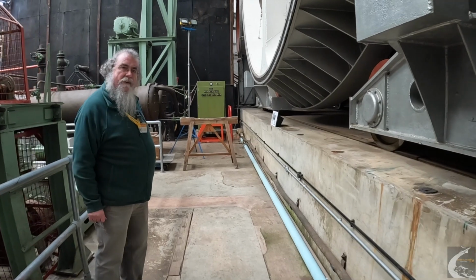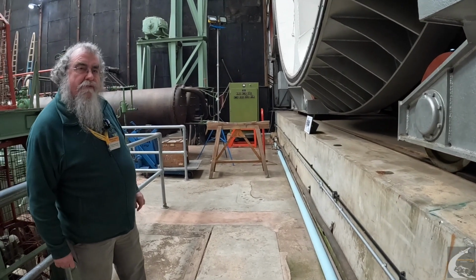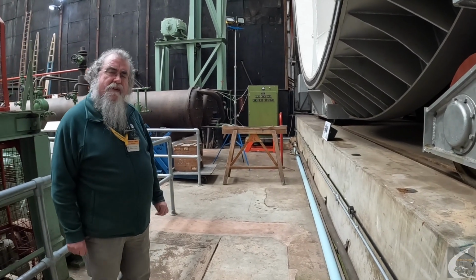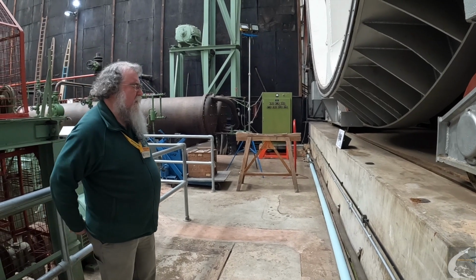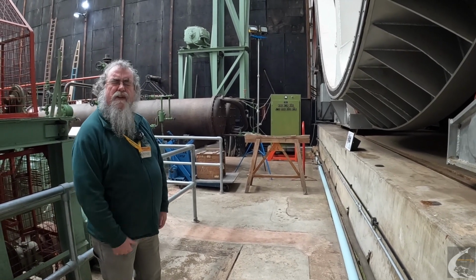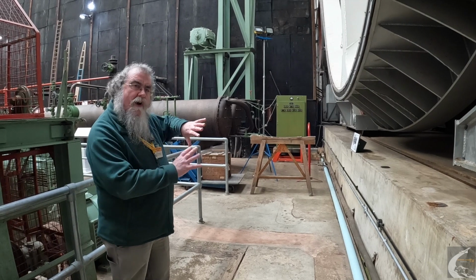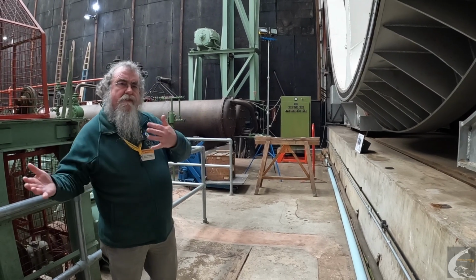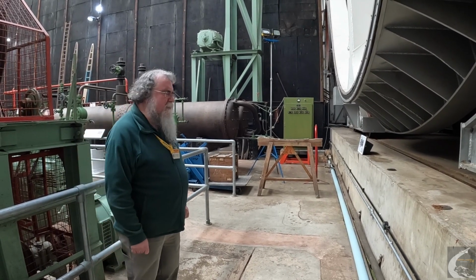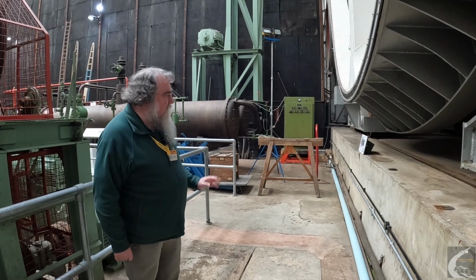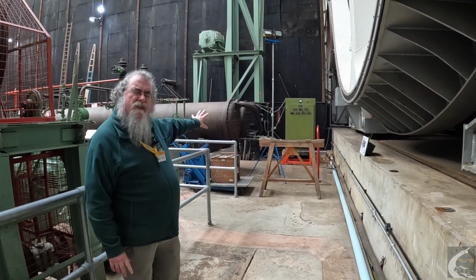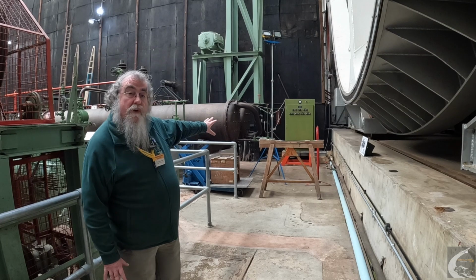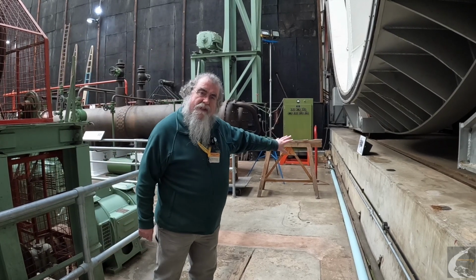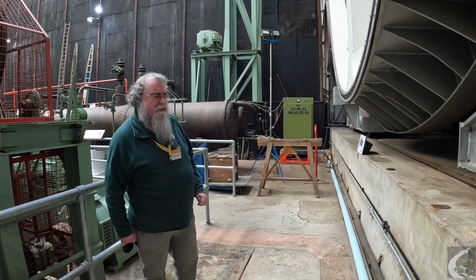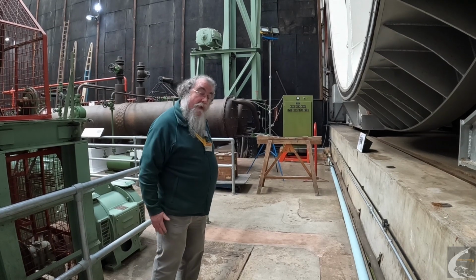That green cabinet is the control for the heating system underneath the chamber. As stated in the introduction, you could warm the temperature in the chamber up to 40 to 55 Celsius - quite warm. To do that, there's a whole load of heater blocks underneath, which we looked at in the video I did under the chamber, which you should go and watch if you haven't already.